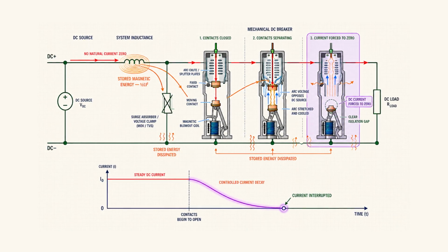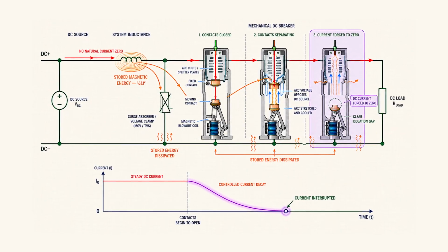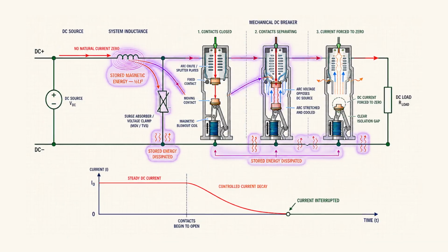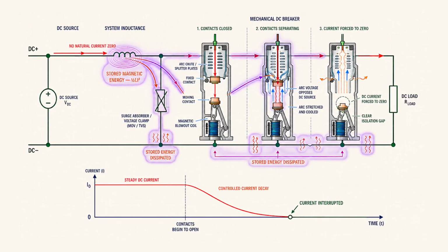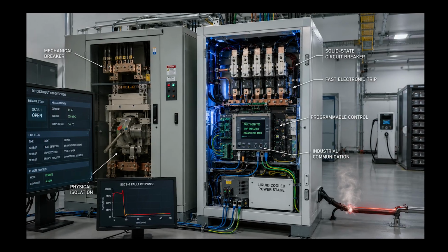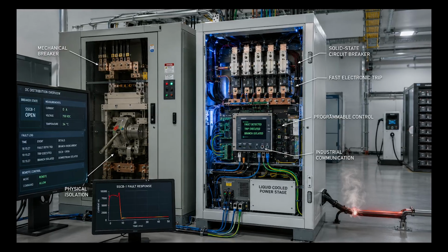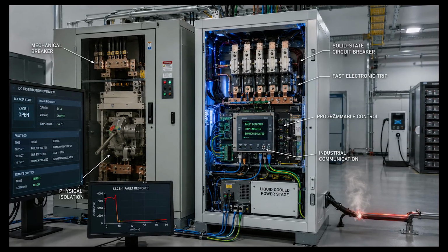So it's the responsibility of the circuit breaker alone to force the current toward zero and also manage the energy stored in the electric field generated by the separating contacts. That is what makes high power DC interruption particularly challenging. With the rise of high voltage DC distribution, the challenge of DC protection is being rapidly noticed by the industry. The purpose of solid state circuit breakers is not to replace mechanical circuit breakers, but to fill those applications where that kind of speed, control, and system integration can't be fulfilled by mechanical circuit breakers, and that is the uprising of DC distribution and DC networks.